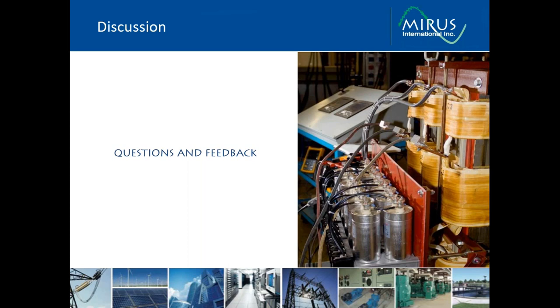There is an application where variable speed drives are used to supply a three-phase motor when only single phase is available. In that application, we do have a device, an input filter designed specifically for that, that will reduce the harmonics and actually improve the operation of the variable speed drive and reduce its derating requirement. So in that application, we do.